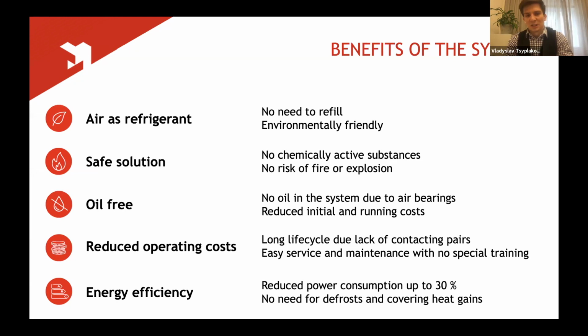So secondly is the safe solution. We don't have any chemically active substances and there is no risk of fire or explosion because we don't use oils in our system. We also have an oilless compressor design, but we use air bearings. So this results in reduced initial and running costs for the machine. So you have less downtime for maintenance, oil refills, oil changes, etc.